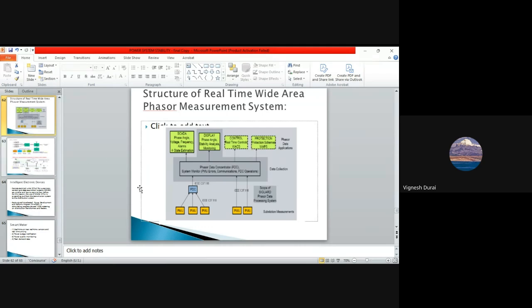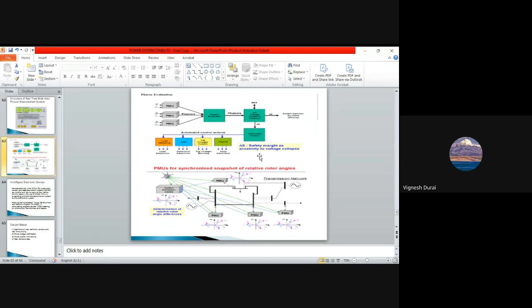Okay. Next. For example, a PMU will have voltage and phasor data or current and phasor data. It will evaluate against the reference. If it is not within the safety limit, they will either go for load shedding, or they will go for generation rise, or they will go for tap changing of the transformer to adjust the voltage, or they will go for reactive devices to boost up the voltage. Anything can happen. It means that they will monitor the system by themselves.